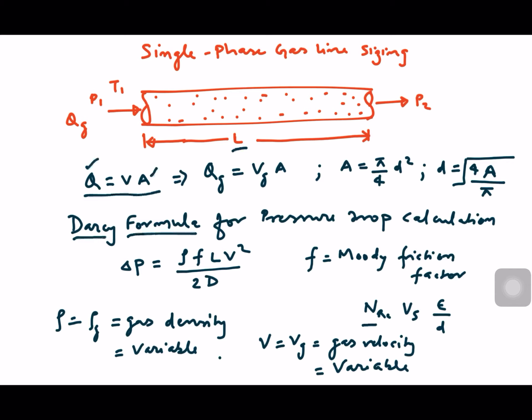We use the Moody friction factor chart to get the value of f based on Reynolds number and the e/D value, where e is the roughness factor of the pipe based on the pipe material. Now, why can't we use the same formula for single-phase gas line sizing? In the gas case, as the gas moves through the pipe there is a pressure drop, and because of that pressure drop the volumetric flow rate Qg changes — the gas expands, its volume increases, and therefore the volumetric flow rate increases. So Qg is variable, and velocity is also variable.